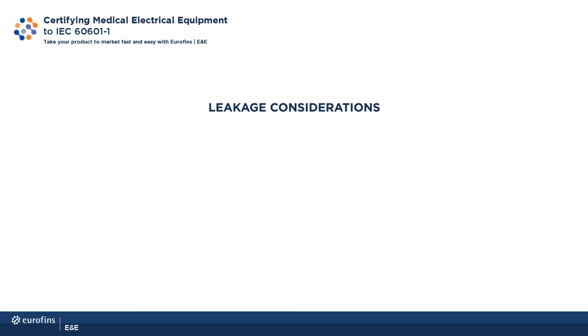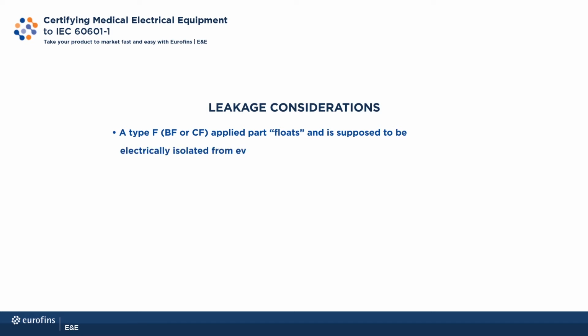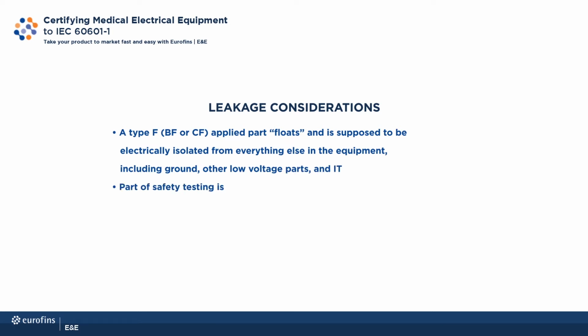Leakage testing is very special for medical electrical equipment. As we discussed earlier, patient leakage is the current that can pass from an applied part through the patient to the ground. Patients with open skin are more susceptible to leakage current. For this reason, many components of medical electrical equipment are designed to be electrically isolated. And to verify this, we perform numerous patient leakage tests. We may measure up to 6 different combinations of electrical situations to make sure that current cannot harm the patient.